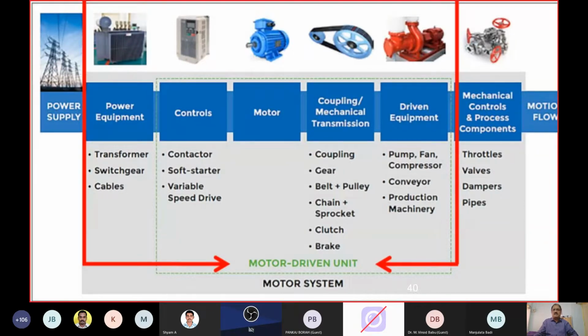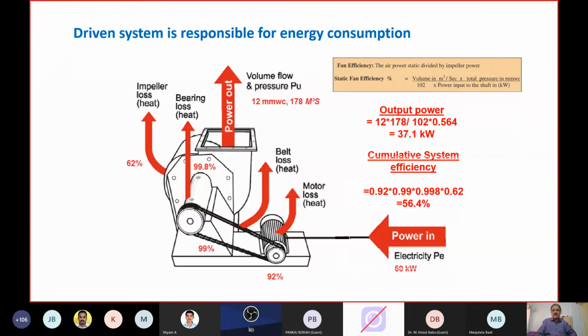This slide will tell you what are all the factors that affect the motors internally and externally. Power quality will have an impact on the motor performance, as you all know. And the equipment used for transmission and distribution of power, like transformers, switchgear, and cables, will have an impact, cables in terms of voltage drop and so on. Then the controls like contactors, soft starters, and variable speed drives have an impact on motor performance. The motor by itself has inefficiencies built into its system by age-old practices. Couplings and mechanical transmission elements have an impact on the performance of the motor as well as the efficiency of the system. Driven equipment and their efficiencies and internal losses also have an impact. And the mechanical controls and processes like throttles, valves, dampers, and pipes also contribute to the overall energy efficiency of the system. So when one undertakes complete energy efficiency, they should factor in and consider all the kinds of losses in the total system. We call it cumulative efficiency.